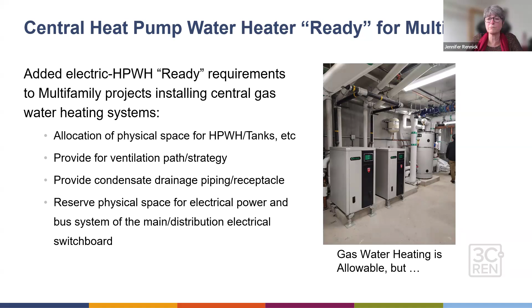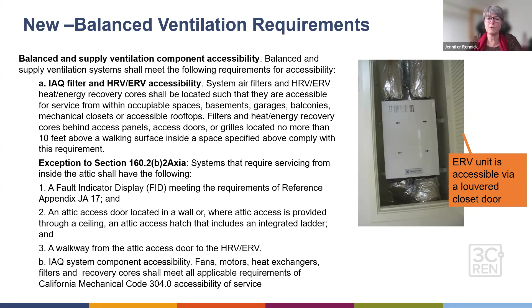And then there was quite a bit of new language on balanced ventilation requirements. I put this whole bit of the code in there for you for reference, but the bottom line on this one is that a balanced ventilation system or a supply only ventilation system is what we're looking for in multifamily projects now. And when you bring in your fresh outside air with a balanced system, the controls or the filters and everything needs to be accessible. So for example, this energy recovery ventilation unit in a multifamily project we worked on, it was easily accessible by a louvered closet door in the hallway where it was set up.